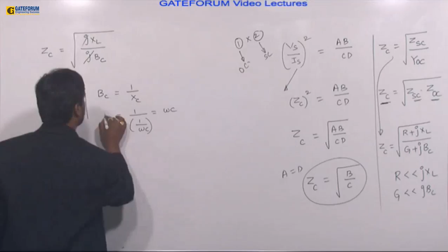Square root of L by C. Practically, the Zc value for an overhead transmission line, OHTL, is designed as 400 ohms. For underground cable, the same formula applies, square root of L by C, which is 40 ohms for UC, underground cables. We will discuss in overhead lines and underground cables why the impedances change, and what effect is dominating in overhead lines and in underground cables at the time of comparison. These are the characteristic impedances of the overhead line as well as the underground cable.